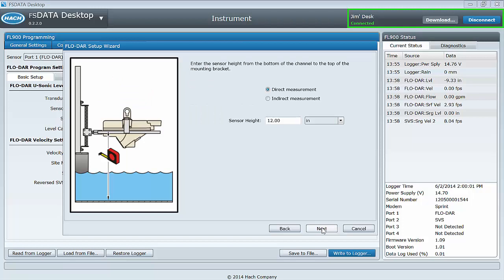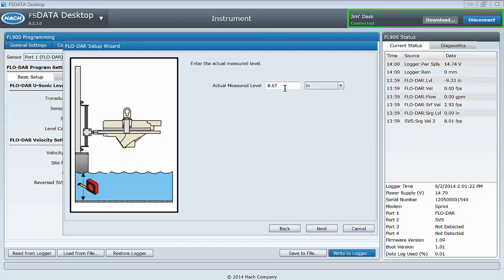Select the measurement method for calibrating the ultrasonic level. Direct measures the distance from the bottom of the channel to the top of the frame and is the most common method used. Indirect requires you to measure the depth of the water and enter that value.